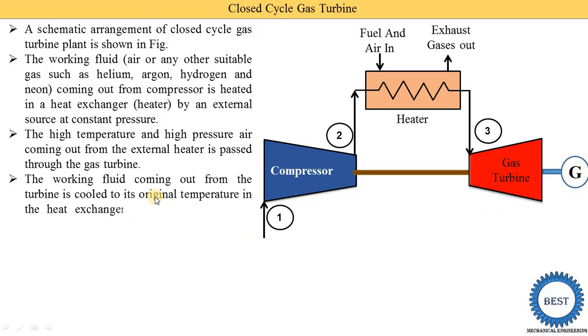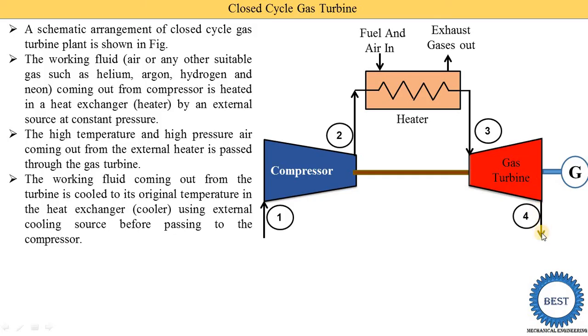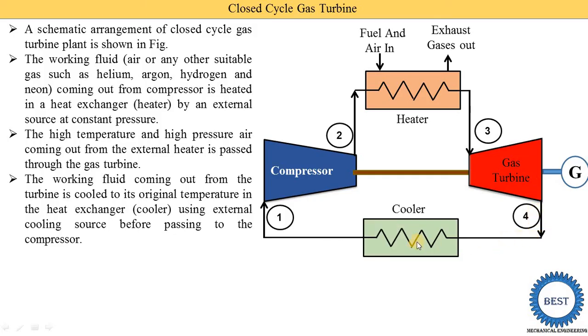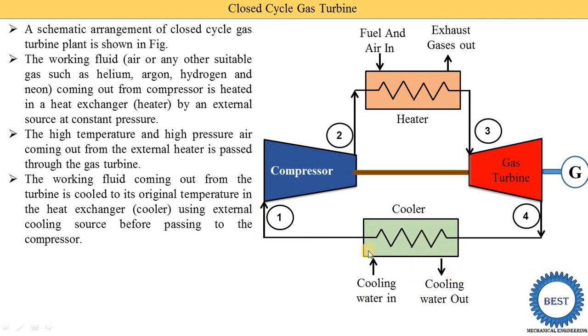The working fluid coming out from the turbine is cooled to its original temperature in the heat exchanger called the cooler, using an external cooling source, before passing to the compressor. The exhaust coming out from the gas turbine at point 4 is connected with this cooler. To reduce the temperature of the working fluid, cooling water is supplied to the cooler. The working fluid passes inside the tubes and cooling water is outside; the cooling water absorbs heat energy from the working fluid, reducing its temperature before it is supplied to the compressor.